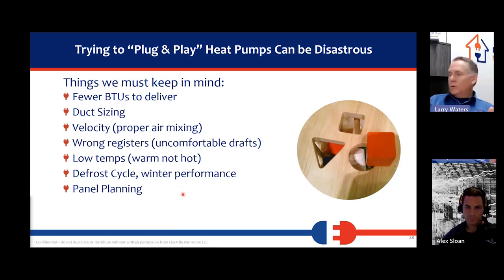Panel planning. When we as HVAC professionals go out to a house that has a furnace and air conditioner, and we put in a new heat pump system, and we add a strip heater, and we add a new line, or we recommission the dedicated circuit to the furnace as 220, or in some cases I know they've got these 110 blower assembly things now. So that kind of solves one problem. But what we're doing is adding load to the panel instead of reducing load to the panel.